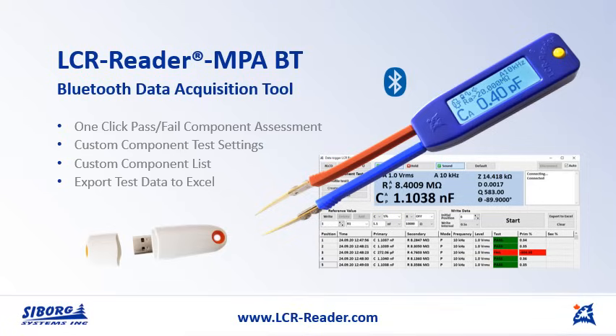LCR-Reader-MPA Bluetooth. This is a wonderful MPA model that has a Bluetooth connection to the computer. Therefore, it allows not just to measure, but also to document the measurement results. And even better, it allows you to control the device itself, the test conditions, from the computer, by setting the conditions on a computer according to the value that needs to be measured. So this device is very popular on the production lines and at other places where documentation is really important.